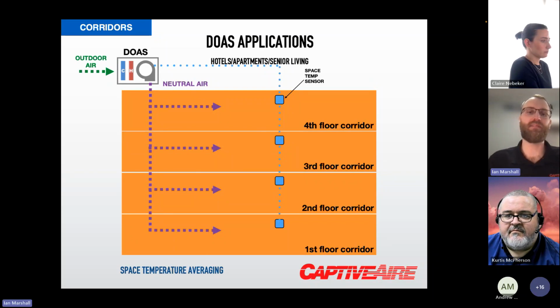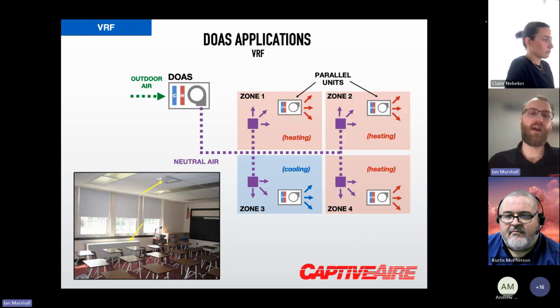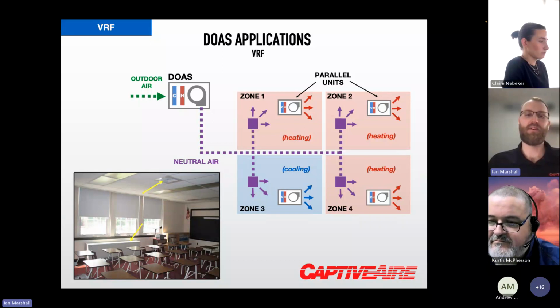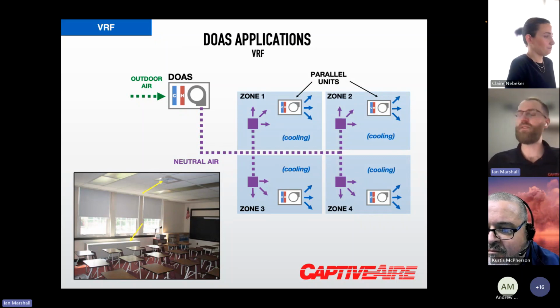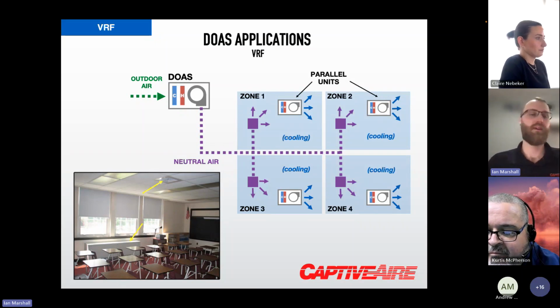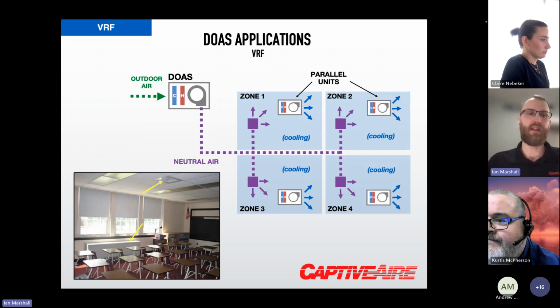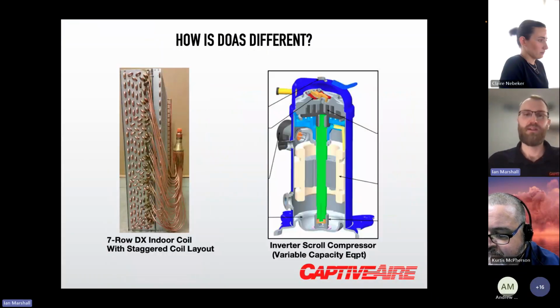And again, many of these spaces have multiple floors. We have the capability to do space temperature averaging throughout multiple different floors if needed. Same on VRF, or when we're talking about terminal units where we're providing the neutral ventilation air, and each one of those individual spaces could be doing their own heating, cooling loads, and we're just providing that simple dedicated fresh air for the space at a neutral 70 degrees at 50% RH or so.